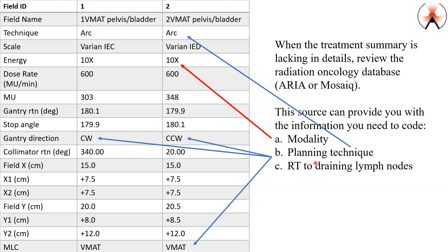But if you want further confirmation, look at gantry direction — that's that big portion of the machine. If the patient is lying on the table and I have the gantry at zero degrees, it's right over the patient's head. I can rotate that — remember, 180 degrees in either direction. The gantry rotation information is telling me in which direction the gantry is going to be rotated for the first field of treatment.